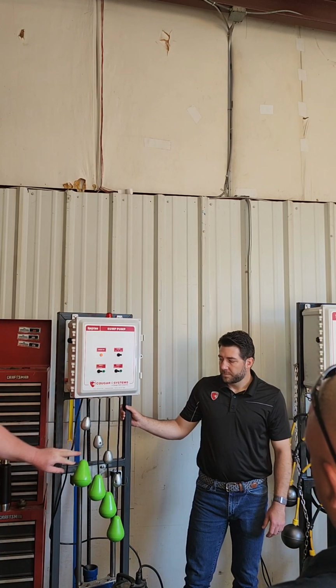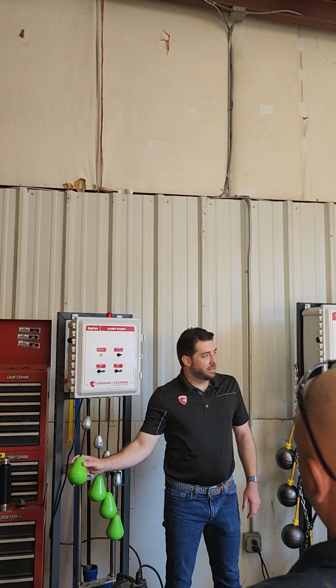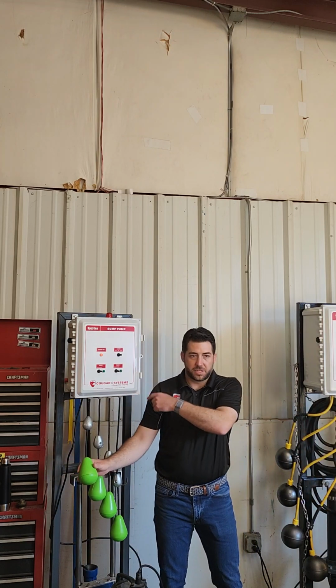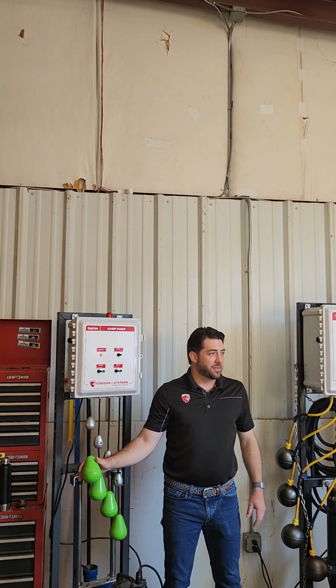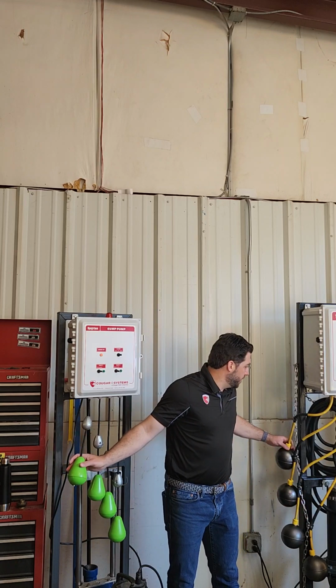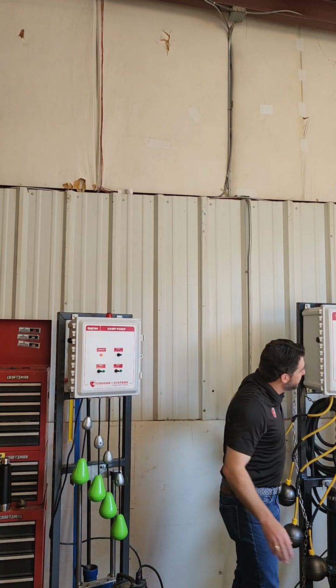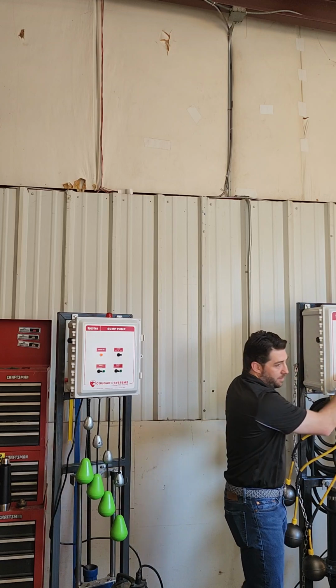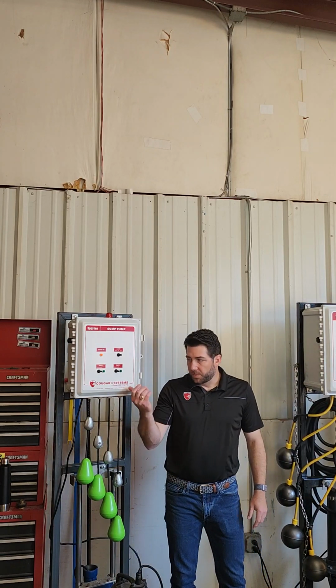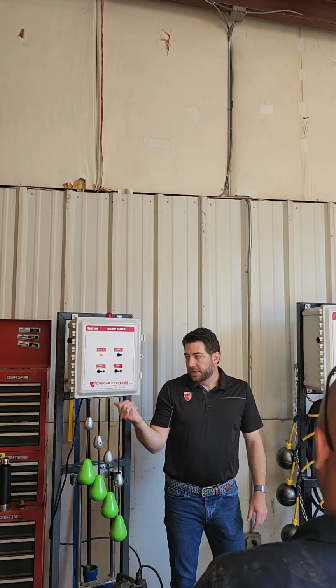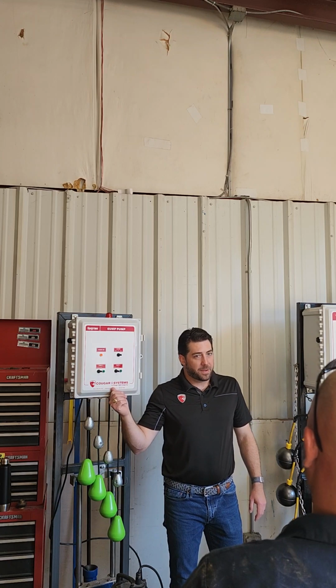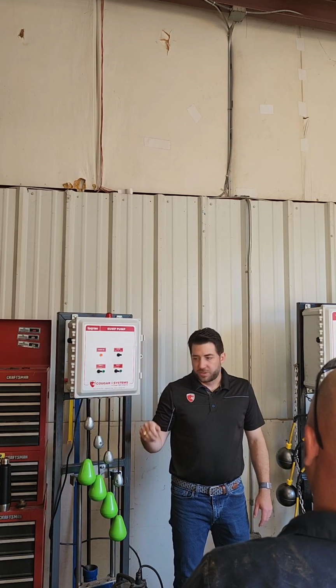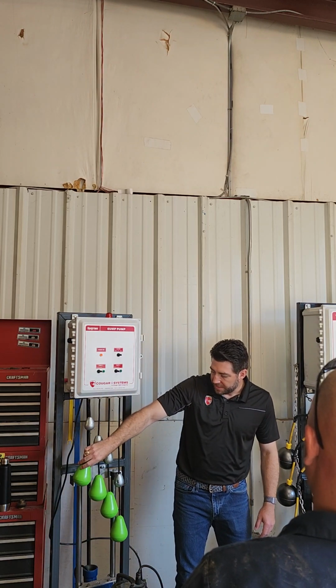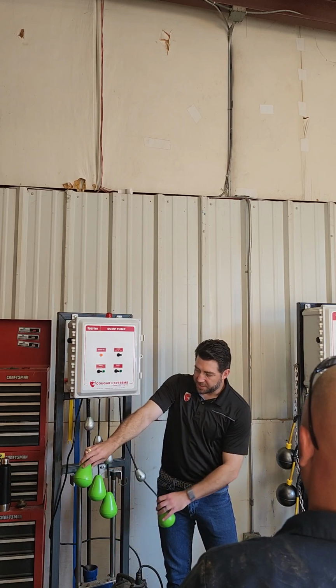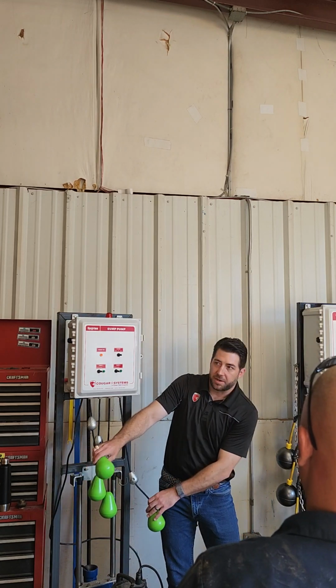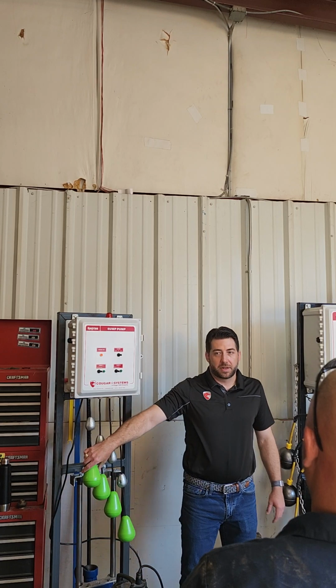Okay. So one thing on the high level alarm. On this one, you notice it's just an alarm, so nothing else is happening. So on this one, when we do the alarm, remember how many floats? It brings on the pumps, right? So the way that we build these now, it does bring on the pumps, but most other panel makers don't. So basically what that means is you don't have any second layer protection if this float fails, right? You're going to get that alarm, but you're still going to have a full pit.